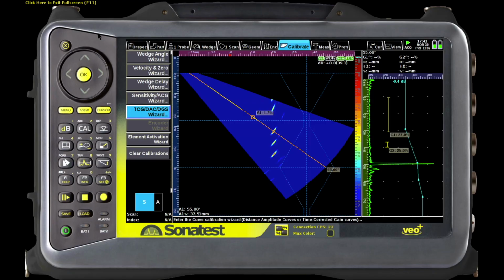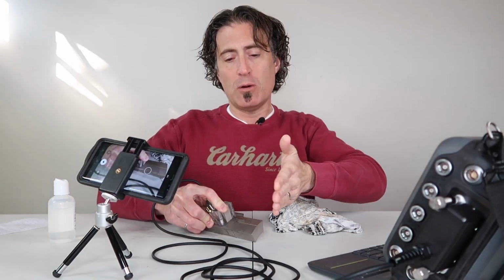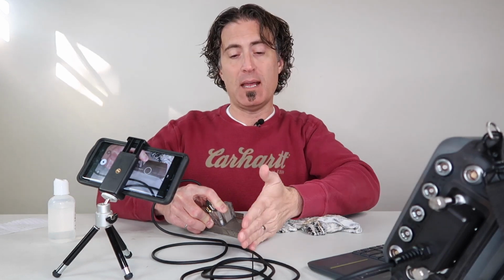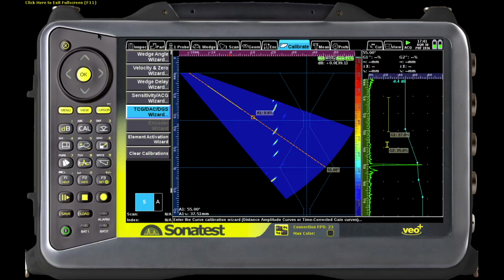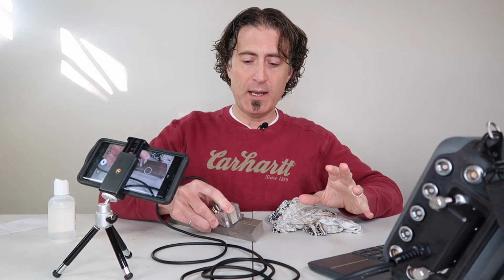Now we're done our TCG. We can see that we've got our 3 hole signals lined up nicely on the first leg and into the second leg and even into the third leg. And you can also see that there is no termination echo from the end of this block, even though the holes are only about 1.5 inches from the end. And that's because the end of the block is tapered and we don't have the high angles and low angles talking to each other. Now we finished our TCG, and there's one more thing we can do.